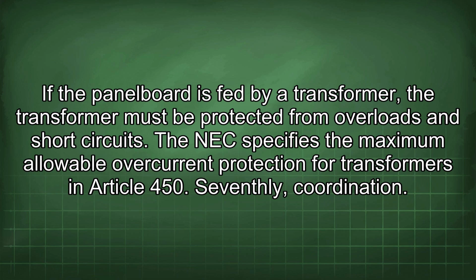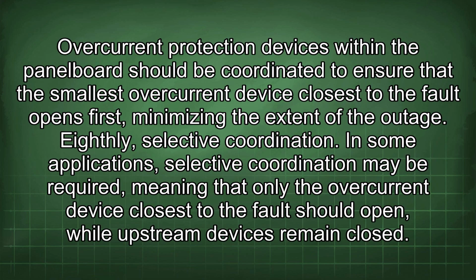Seventhly, coordination. Overcurrent protection devices within the panel board should be coordinated to ensure that the smallest overcurrent device closest to the fault opens first, minimizing the extent of the outage. Eighthly, selective coordination.